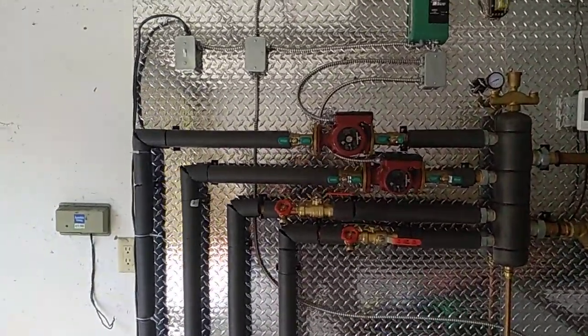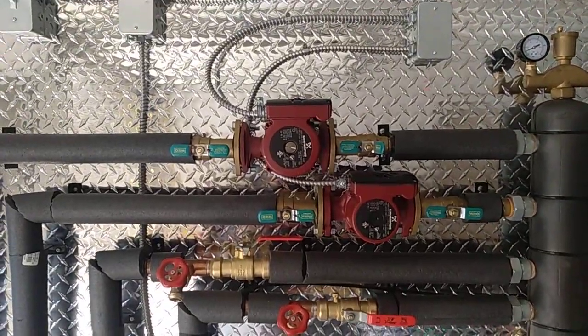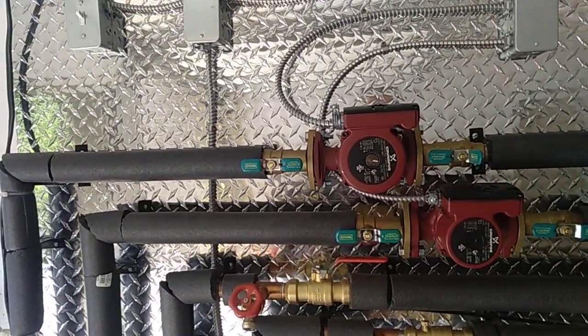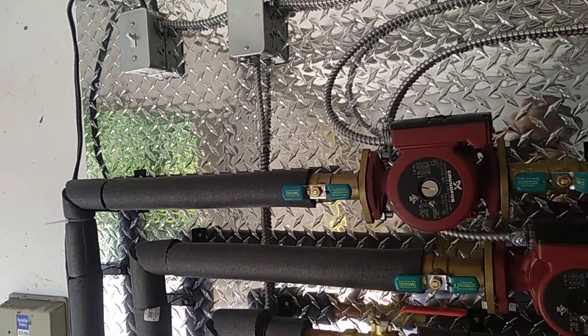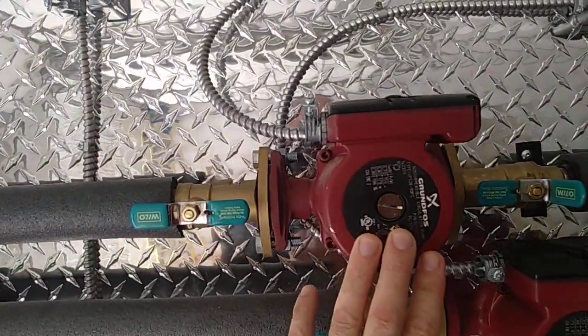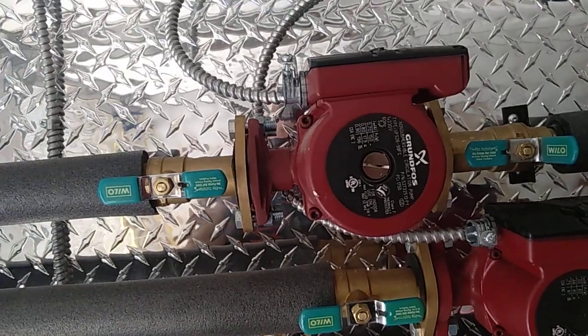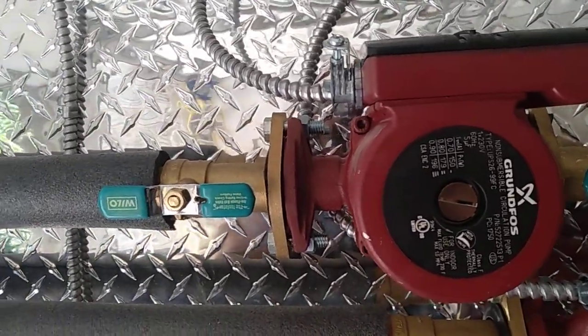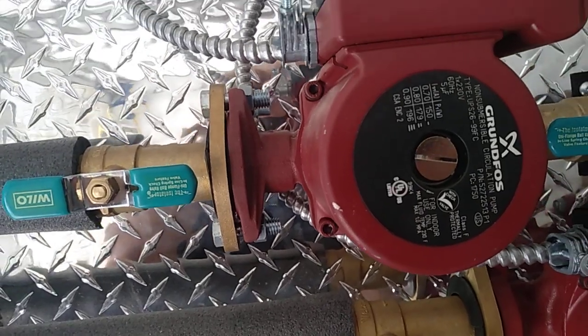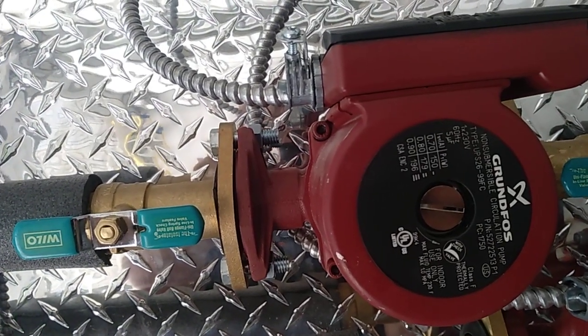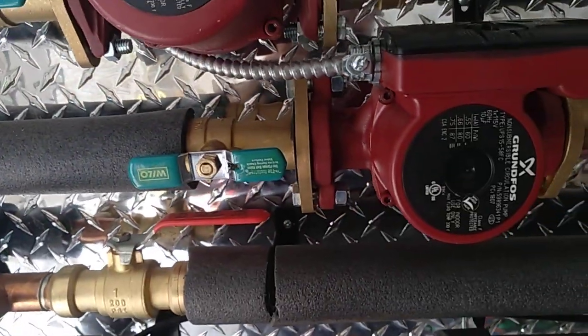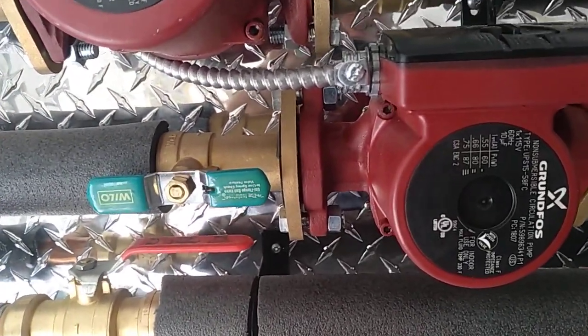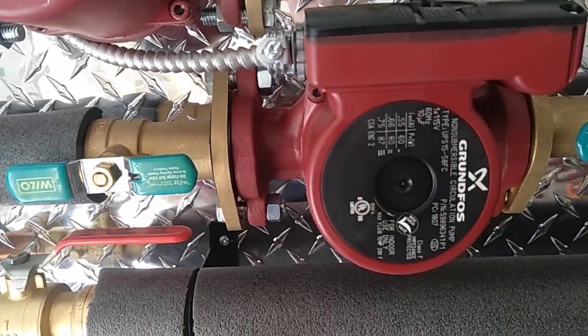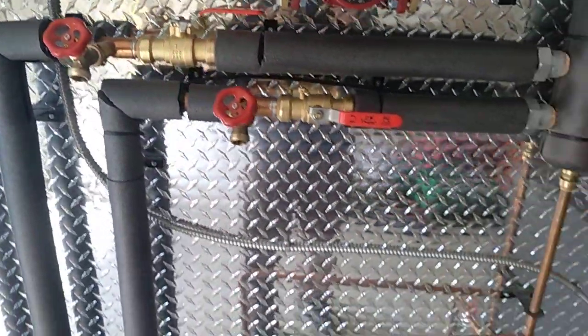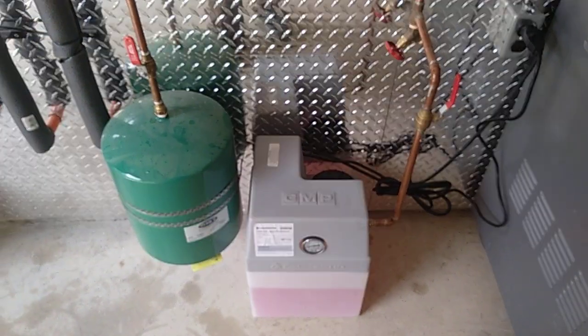There are two manifolds out there, and they have two pumps dedicated to it. The first manifold has 8 loops, 3/4 inch shark bite tubing, and that is powered by a Grundfos pump. To be exact, it's a 26 series pump, and the smaller manifold 4-loop is driven by a 15 series Grundfos pump. And the system is filled with glycol and water mix 50-50.